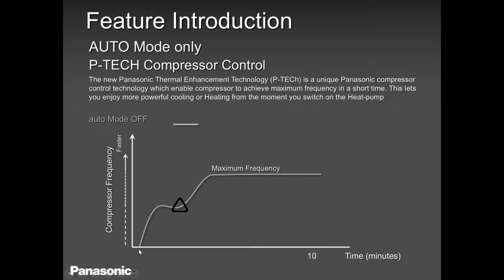For the first 3 minutes, it's going to run at a very low frequency and obviously lower amps. So please, I beg you again, don't conclude that you have a problem with refrigerant or the compressor or the inverter PCB. For the first time, the compressor is going to run very smoothly, very slowly, and it's going to pick up. In my experience, start making your conclusions after 10 minutes. After 10 minutes of operation, you will have a clear idea, guys, of what's going on with this unit, whether it's refrigerant, compressor, or anything else.